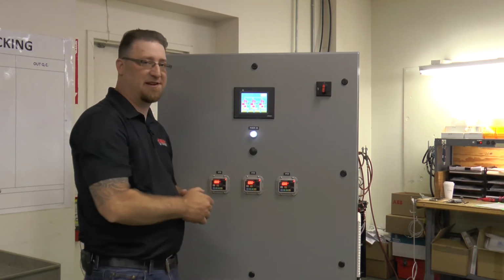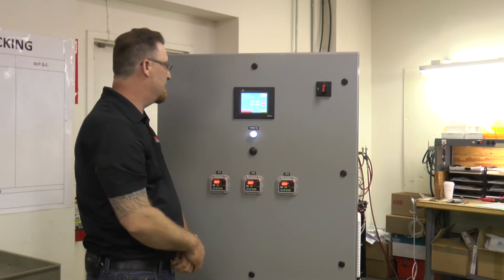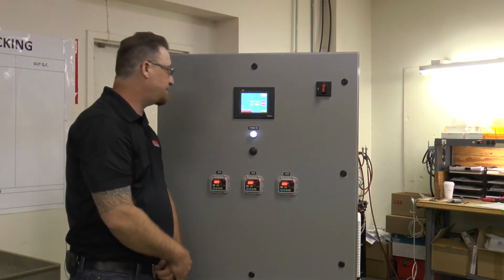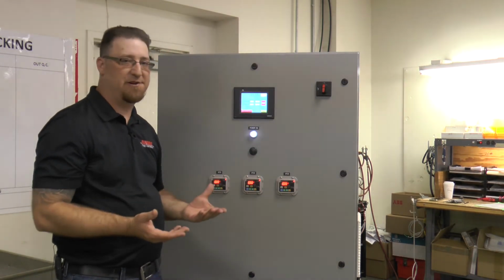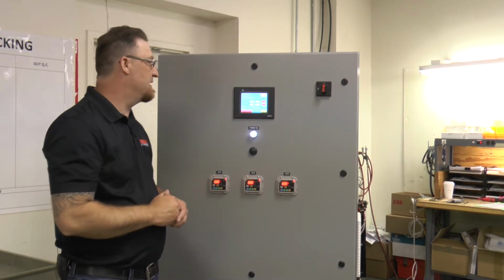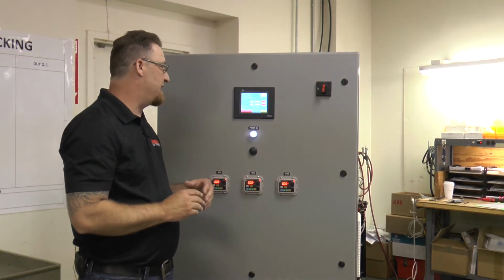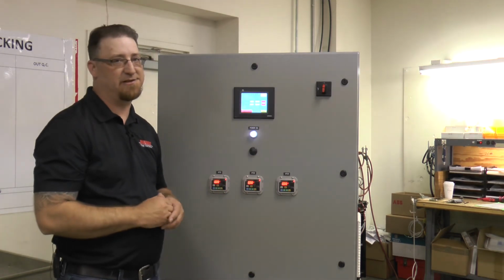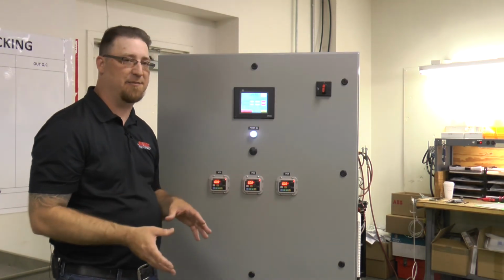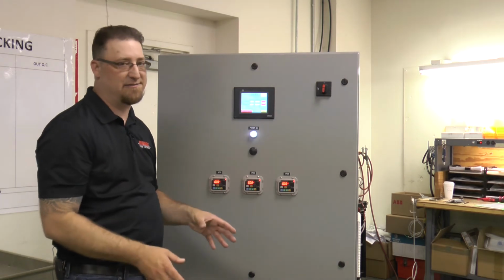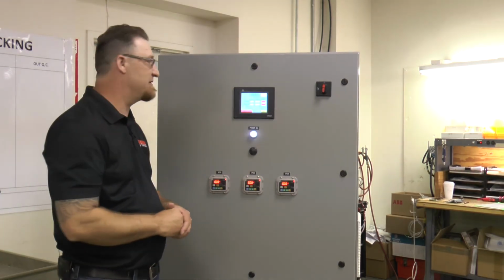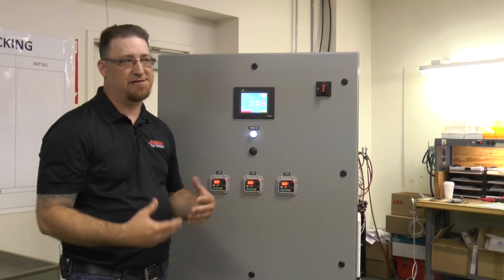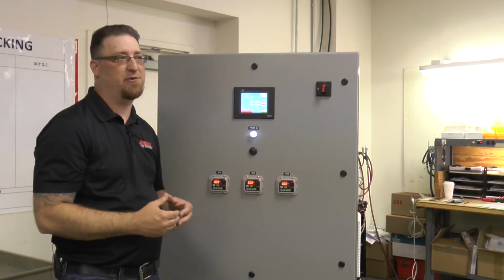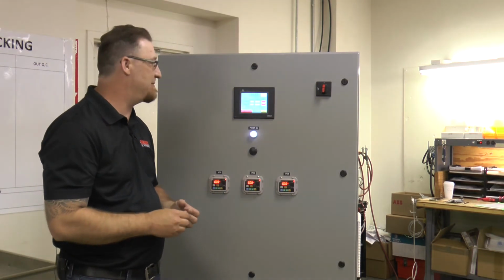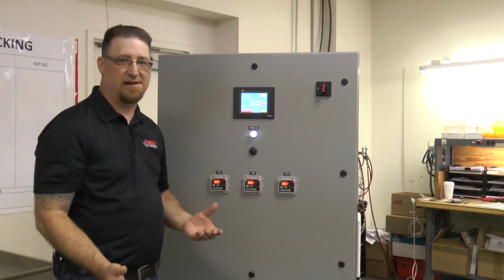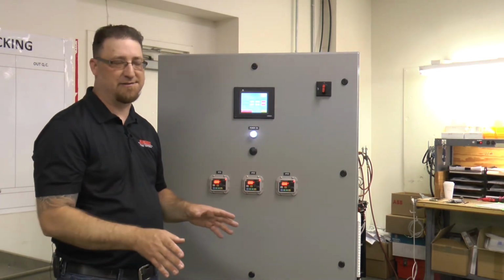We'll go to alarm setup now, and in your alarm setup, we have 2 options. You have low discharge pressure or high discharge pressure. So at these points, at which point on your low discharge pressure should you set an alarm and say, hey, maybe I need to stop the pumps and tell somebody, hey, I have no water at my pumps. Same thing on high discharge. If something goes wrong and you're pushing too much water and getting too much pressure in those pipes, at which PSI should I trigger an alarm and tell somebody?